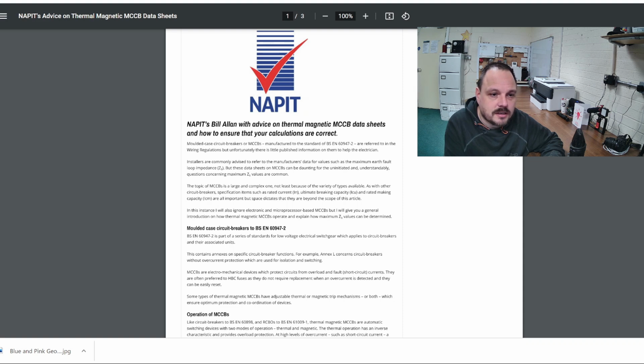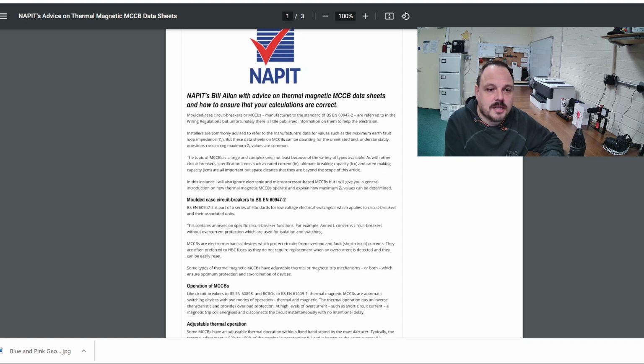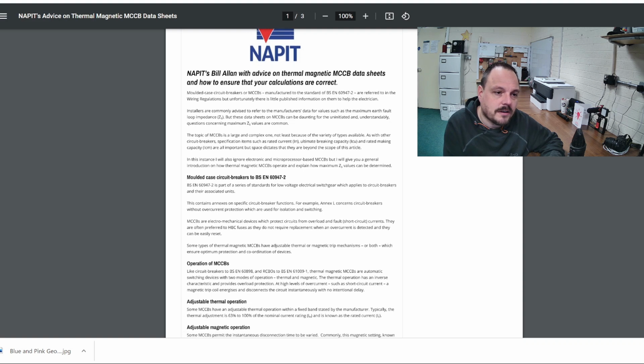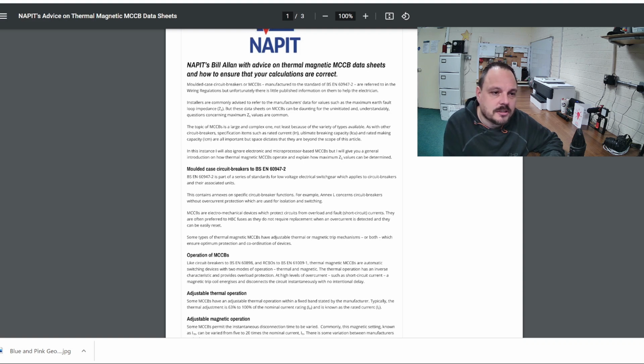And installers are commonly advised to refer to the manufacturer's data for your earth fault loop impedance values. Sometimes these can be daunting, so this actual article is aimed at showing you how you can calculate what the maximum ZS would be, and I'll jump to that in a minute. But I was more wanting to focus on the explanations of how these actually operate. So it says here the topic of MCCBs is a large and complex one, not least because of the variety of types available. As with other circuit breakers, specification items such as rated current, IN, ultimate breaking capacity, ICU, and rated making capacity are all important, but space dictates that they are beyond the scope of this article. So yeah, I totally agree with that. I can see exactly why he said that.